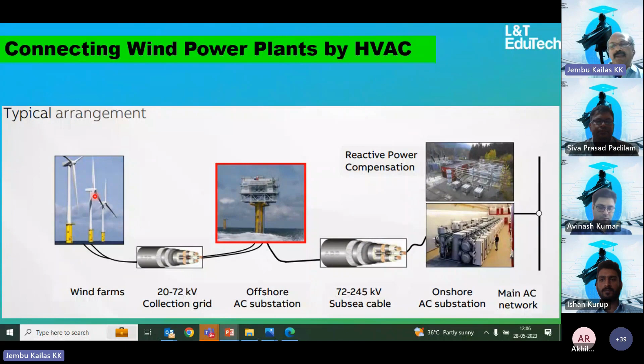This is a typical arrangement of an offshore wind platform. You can see, it means 220 kV GIS - gas insulated substation. We go for gas insulated substation here; we cannot have a conventional substation. Then there's a transformer, 66 kV GIS container, temporary diesel generator, and so many things, then a step-up transformer. Everything has to be accommodated on the platform.